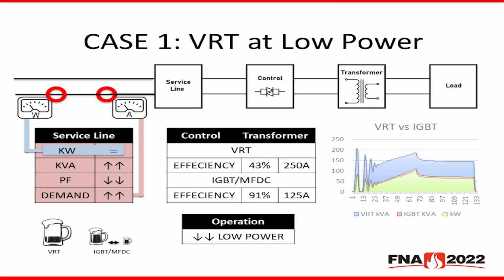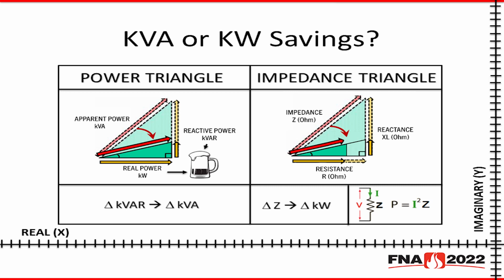If you look at the graph on the right, you have the VRT in blue, and now the IGBT MFDC system in red. You see that the IGBT MFDC system total power is very close to real power in this application. So in summary, VRTs place a disproportionate electrical burden on the power grid, and IGBTs are an adaptable alternative that optimizes use for each use case. Before we move on to case 2, I want to discuss briefly the difference between kVA and kW savings. We went over the power triangle briefly in the very beginning, and this is the beer mug analogy.